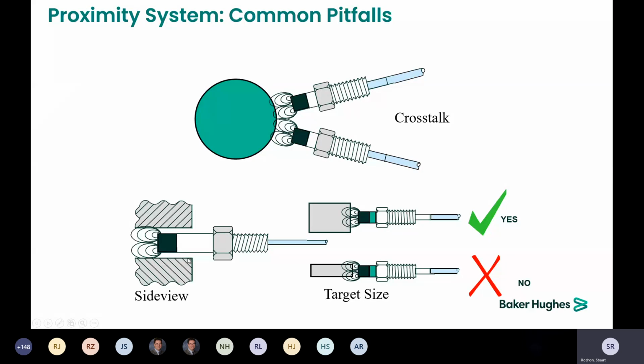Another issue you run into is what we call side view. This is where that radio field picks up material from the side. On installations, we recommend that you have a relief cut near the shaft if the casing comes near to the shaft. That is that 2.5 times the diameter of the tip. And you can actually get to a negative 10 volt gap setting by side view. So one of the things that you need to do is make sure that the probe actually gets down to the shaft and is looking at the shaft, not looking at casing material.